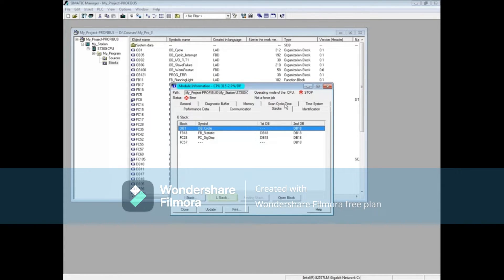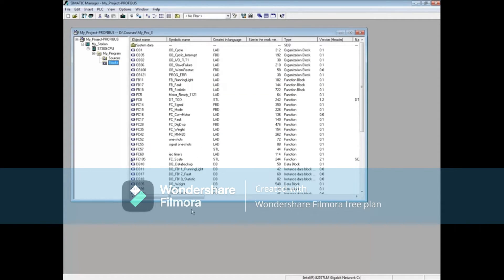The local data or L stack shows the local data values of the organization block that started the call sequence. Stacks is a good choice for more advanced code troubleshooting where you need to see what values are in the different PLC registers at the time of the fault. Keep in mind that the CPU does have to be in stop mode to view the stacks tab.